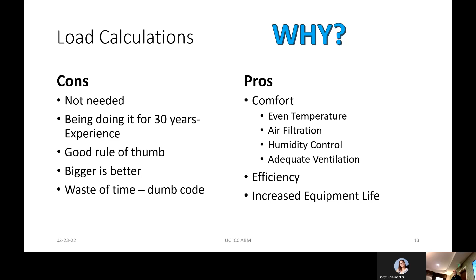No, because there's a bunch of other factors, and number one is that the duct system is often not installed according to the duct design. That's the biggest issue I see out in the field. I have associates in the HVAC and testing industry, and more than 90%—really 94 to 95%—of the time when they put airflow testing equipment on residential HVAC systems, it does not have the airflow it was designed for, because of the duct system.